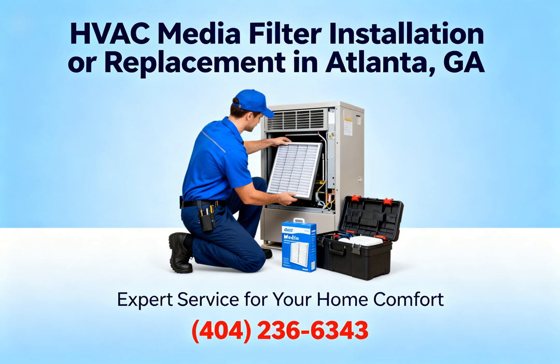Because it's a massive departure from the norm. With standard 1-inch filters, homeowners are accustomed to that nagging 30-day replacement cycle. Right. But because the media filter utilizes 40 times the surface area, the loading capacity has to be exponential, right? It is. In a standard residential environment, a media filter will last 6 to 12 months. 6 to 12 months, that's amazing.